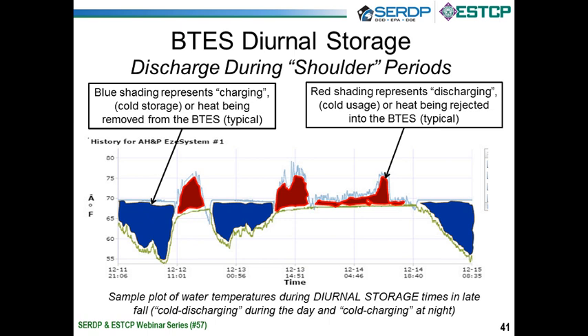And then we weren't really certain this was going to happen, but we ended up with diurnal storage, which we should know that. It gets cold at night, and it's warmer during the day. So in this illustration, the green line, and I'm going to grab this pointer here, represents the entering water. So we're making colder and colder and colder, and that particular night we got down to maybe 53-degree water.